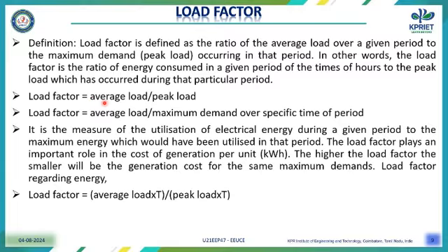We can say that load factor is the ratio of average load to the peak load, or the average load divided by the maximum demand over a specific period of time. It is a measure of the utilization of the electrical energy during a given period to the maximum energy which would have been utilized in that period. It plays a very important role in the cost of generation per unit.